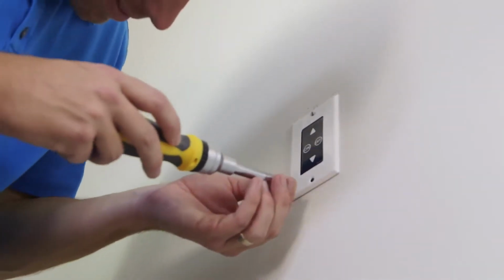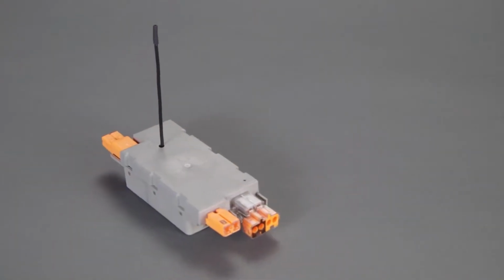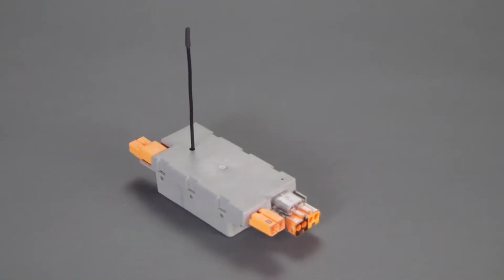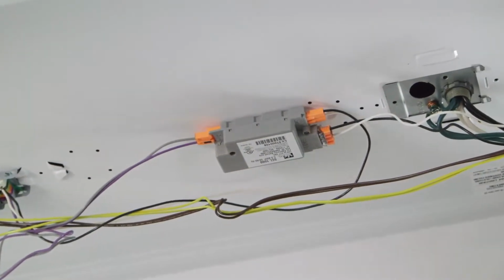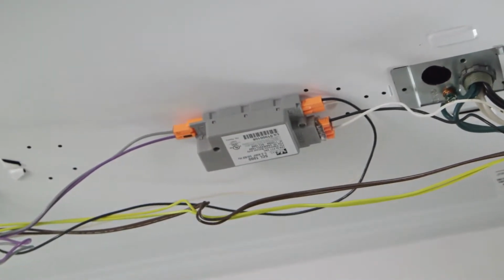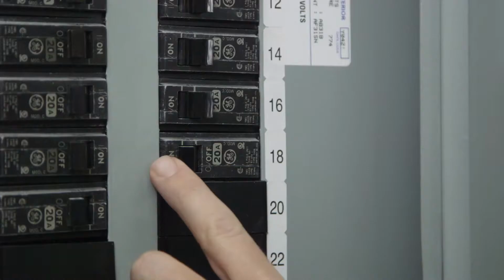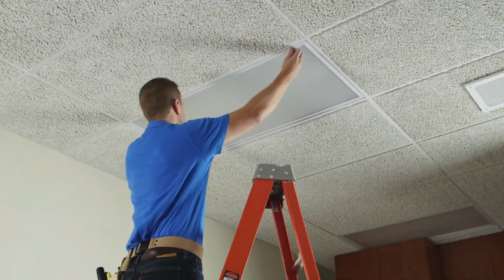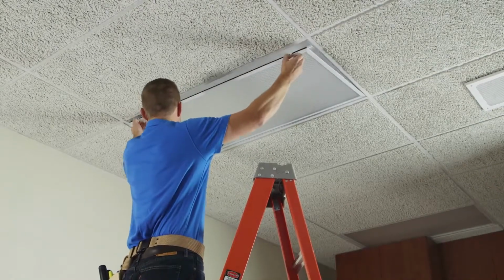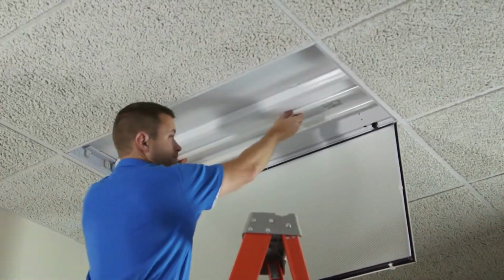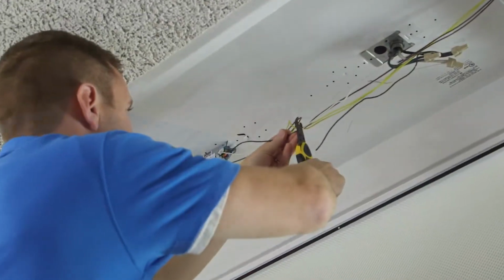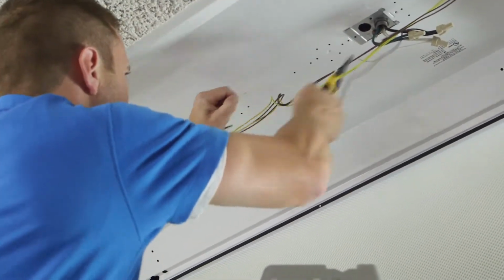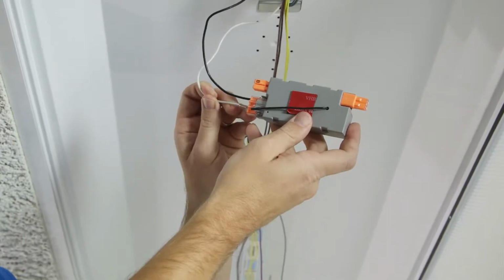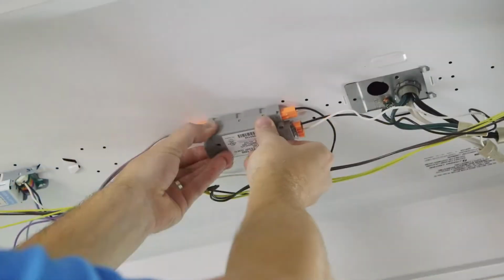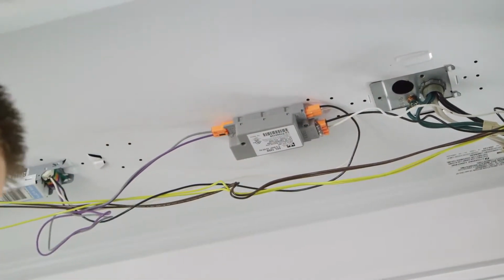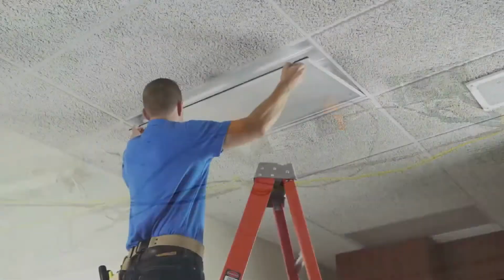The Audacy system also employs easy-to-install smart connectors that physically feed and control AC line power to light fixtures. After turning off the power and gaining access to the fixture surface area, using the push-in wire terminations, the wiring to the smart connector is as simple as cut, strip, and insert. After all wires have been installed, the smart connector simply mounts to the fixture's sheet metal via UL-listed double-sided tape.